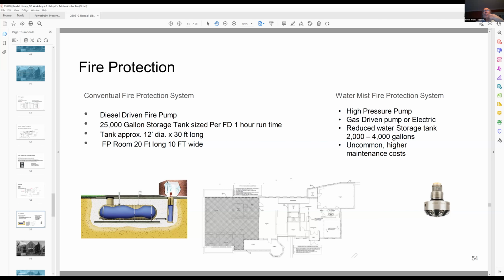So instead of conventional water droplets, this compresses the liquid down to a high pressure. Maybe the best way to explain it is a power washer. You've seen the water coming off of a power washer? Well, that's about 2,500 PSI. This is about 10,000 PSI. So your water droplets are significantly smaller, and it creates a mist in the space. And so you're using about 1/10 of the water per head or even less. That means that we can have 1/10 of the water, in rough numbers, stored. So our storage capacity would be reduced from 25 to 30,000 gallons to somewhere between 2,000 to 4,000 gallons of water, which I think might be a little bit more amenable to finding a home for that on the site.